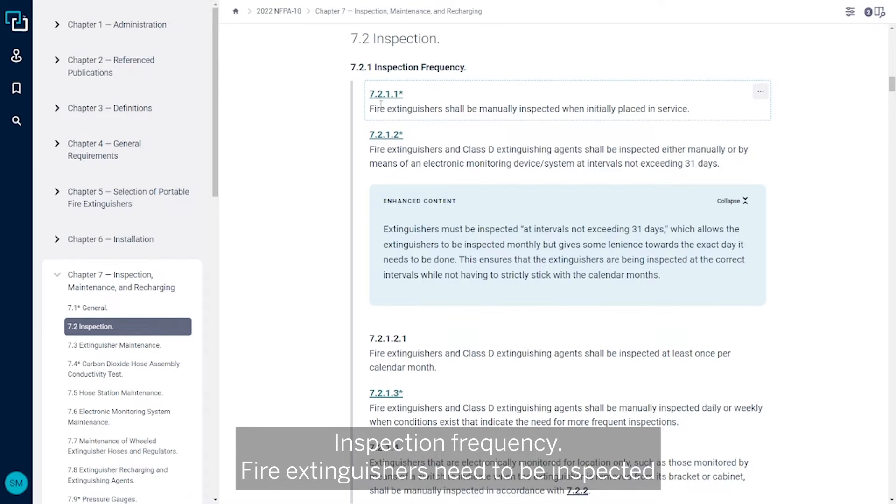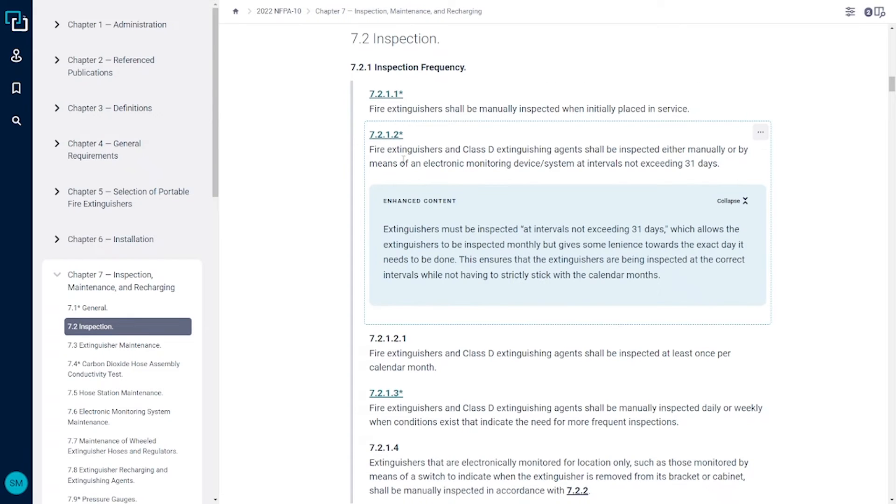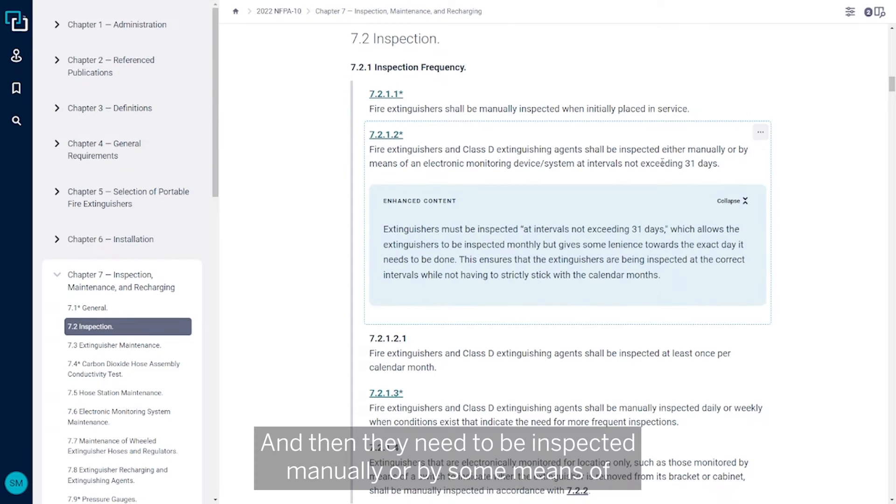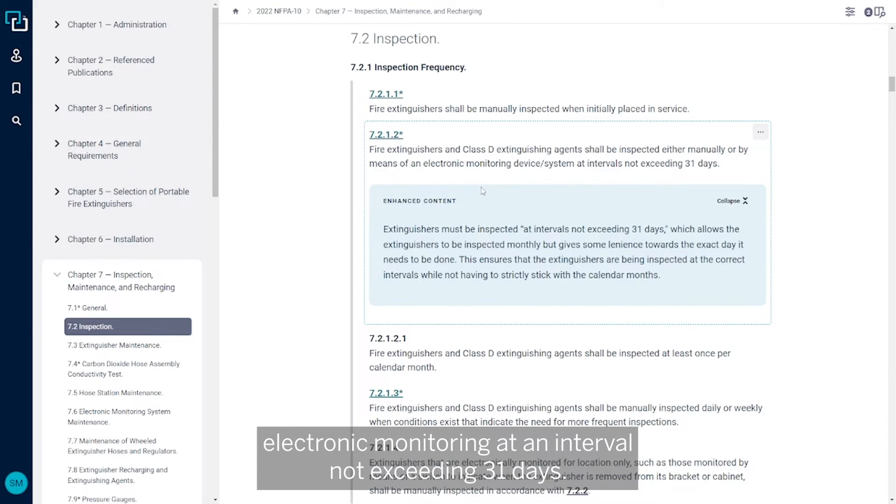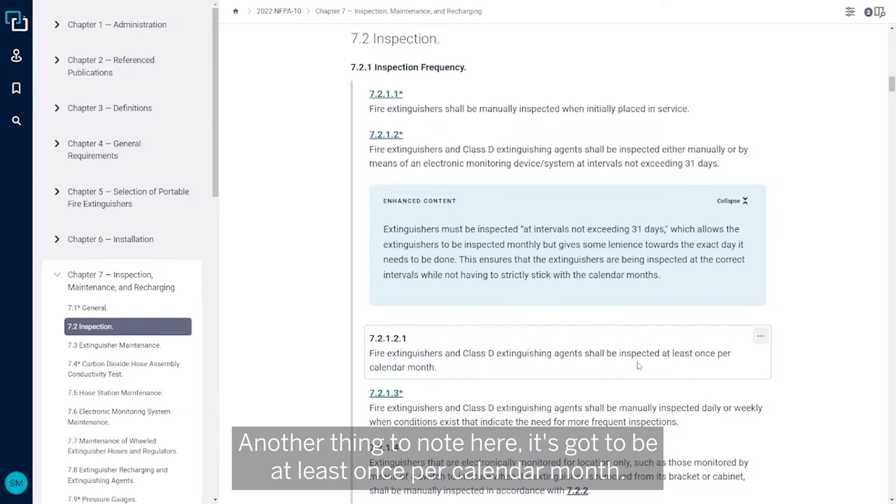Fire extinguishers need to be inspected manually when initially placed into service, and then they need to be inspected manually or by some means of electronic monitoring at an interval not exceeding 31 days.